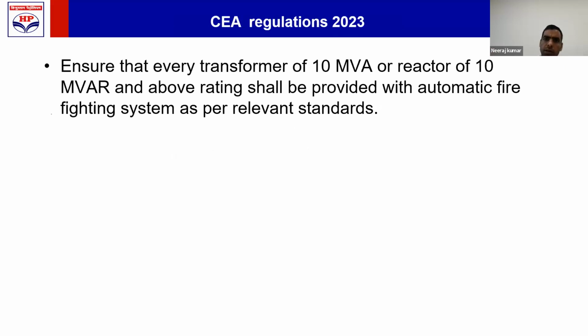Before we go into the detail, recently the CEA regulation 2022-23 has been published, which supersedes all other regulations and other things. This requires that if your transformer is of 10 MVA or more, forget the oil capacity. If it is oil filled and 10 MVA and more, then you are compulsorily required to provide an automatic firefighting system. So OISD requirement and the CEA requirement should be seen side by side.